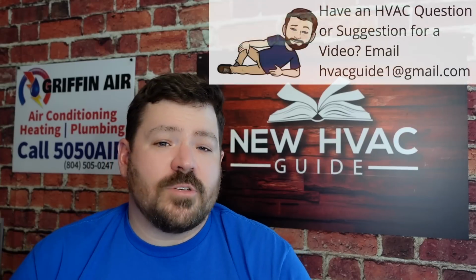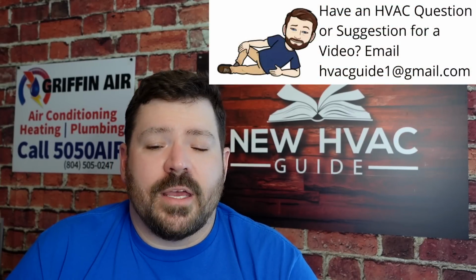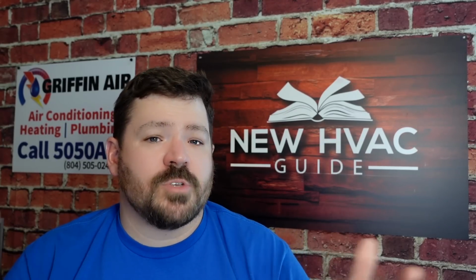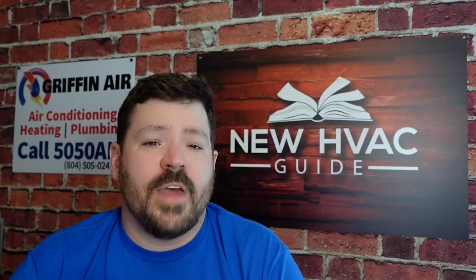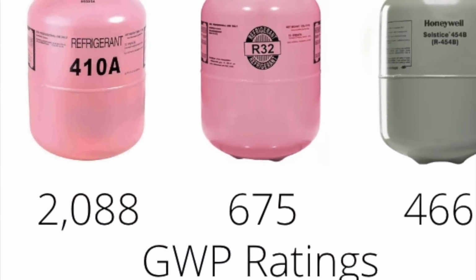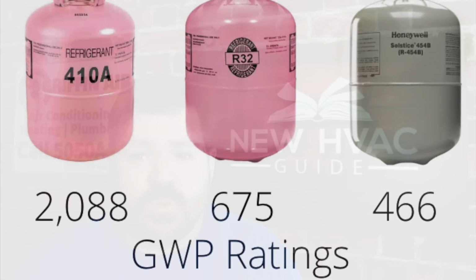And so we're about to wrap up, but the last thing I wanted to point out is, unlike the recent change in California where they said systems could not be sold with a GWP level of 750 or above, this new rule coming out from the EPA has gone even further and said that nationwide, they don't want systems sold above 700. So 700 is going to be your GWP rating. Obviously 410A is much higher than that. And so you're going to see these new refrigerants have to meet those types of standards.